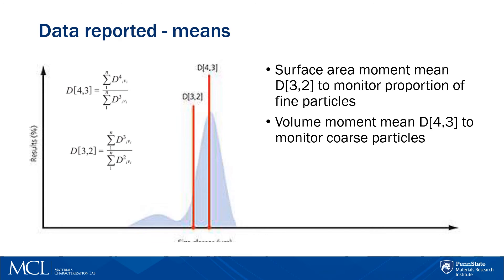D32 is most relevant when surface area is important — for example, when you study reactivity, dissolution, or bioavailability. It is most sensitive to the fine particles in the size distribution. The volume moment mean D43 reflects the size of those particles which consist of the bulk of the sample volume, and it is most sensitive to the presence of larger particles in the size distribution.